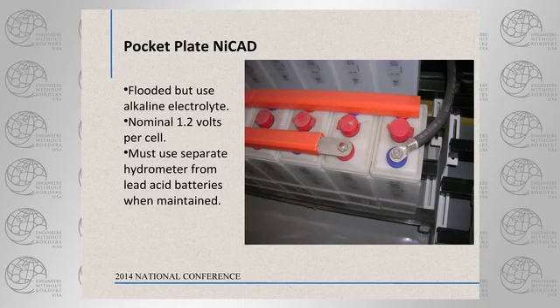I'm going to mention these because you may encounter them, probably won't, but you need to know the difference. These are pocket plate NiCad batteries, a flooded nickel cadmium battery, not like the sealed consumer grade AA or AAA NiCad batteries that are dry, this is a liquid-filled battery. However, this uses potassium hydroxide, a real stout alkaline. So just like with the acid battery, be cautious of the alkaline battery too, it'll eat holes in you the other way. Either way you're going to wind up with trouble, especially if it gets in your eyes. This is a serious eye wash problem for both types of products.